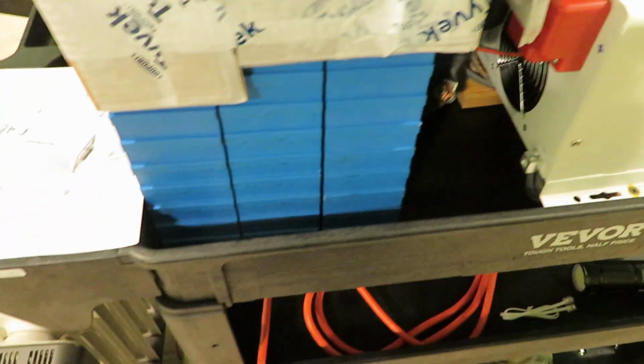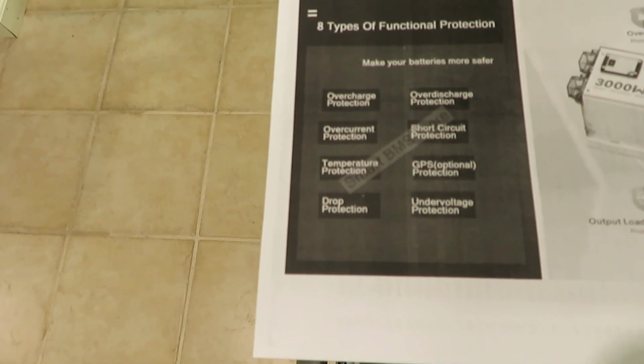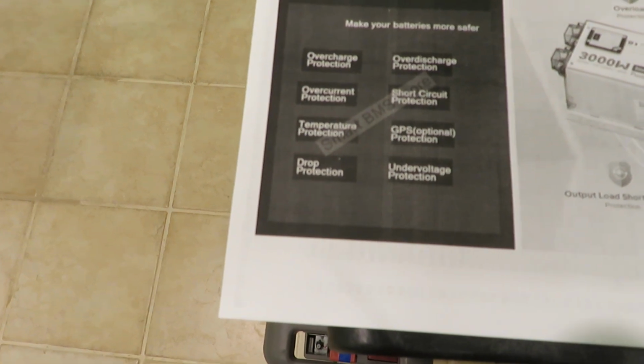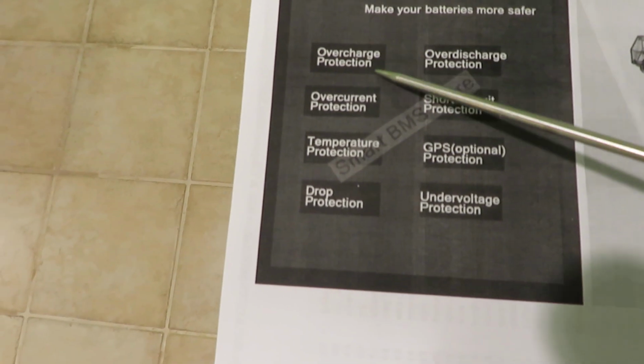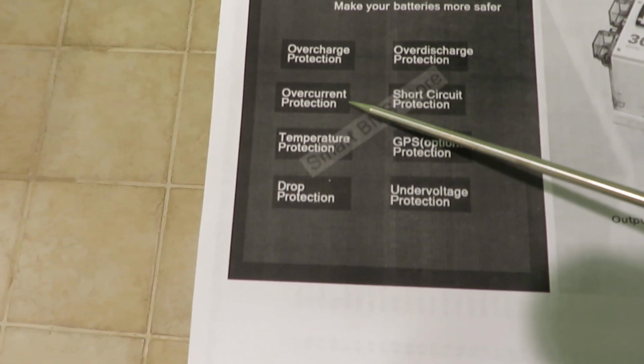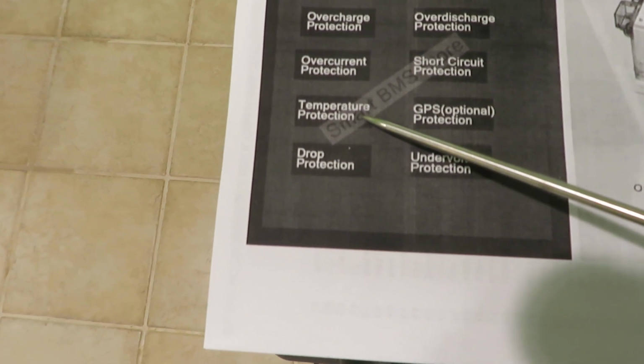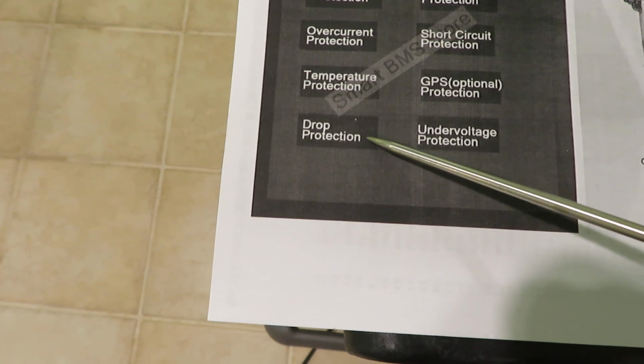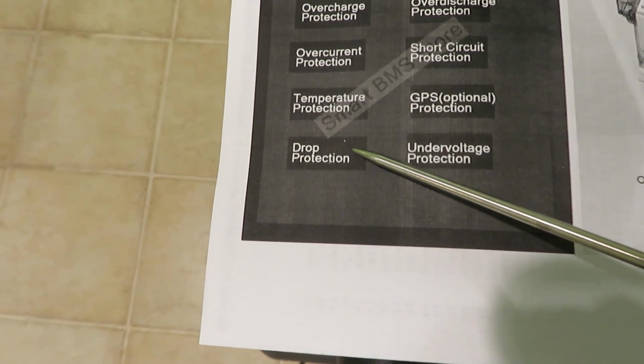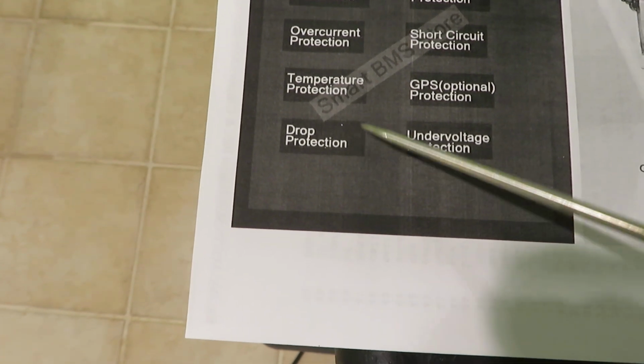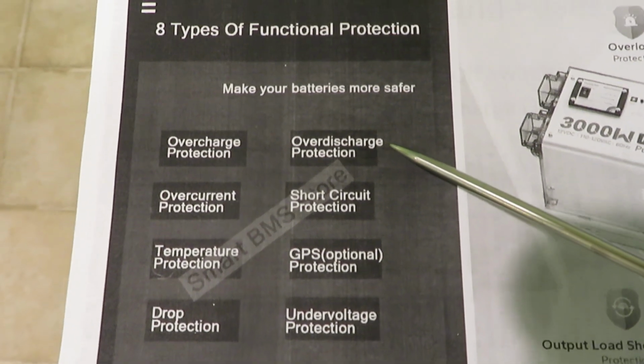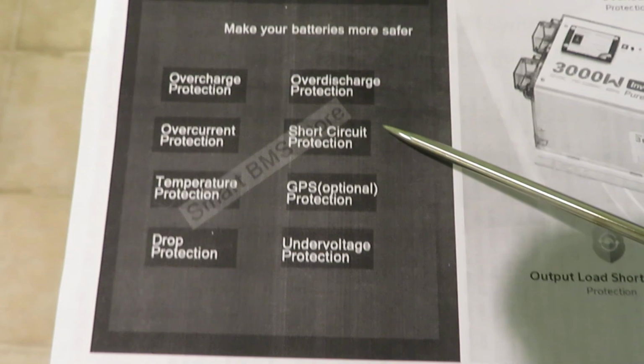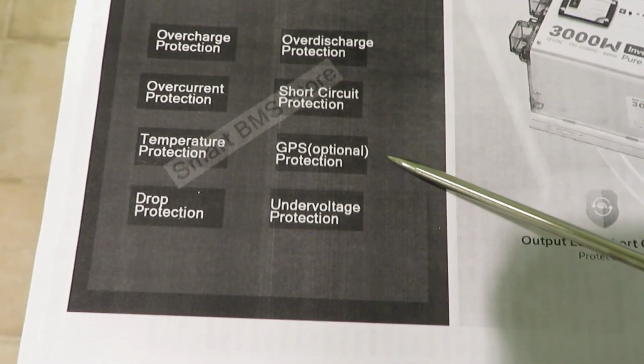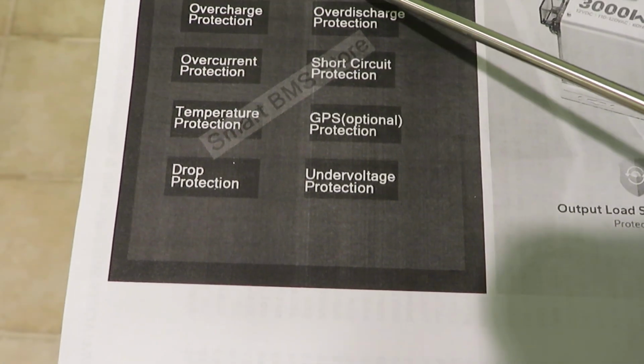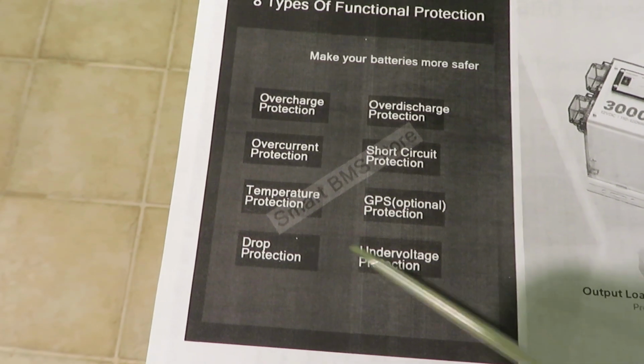Let me share with you some of the safety features the system has. First, let's take a look at the BMS safety features: overcharge protection, overcurrent protection, temperature protection with high and low limits, and drop protection. I don't suppose I would drop the BMS or the battery. Then over-discharge protection, short circuit protection, GPS protection, and under voltage protection. So that's the protection from the BMS.